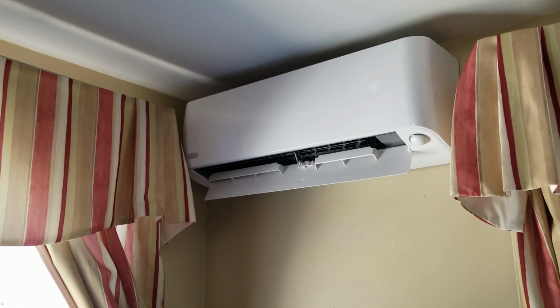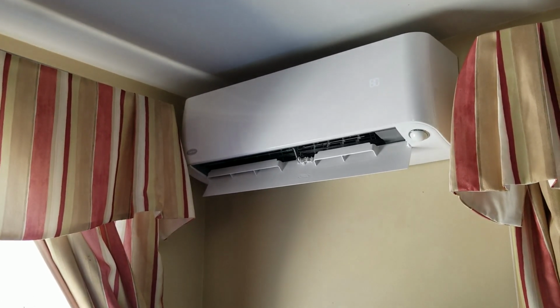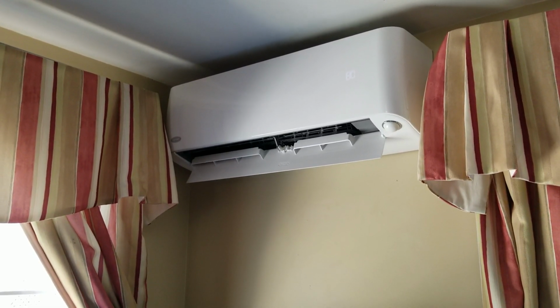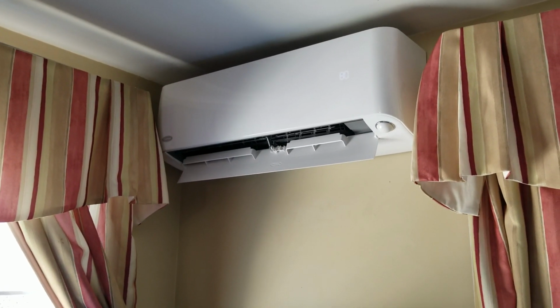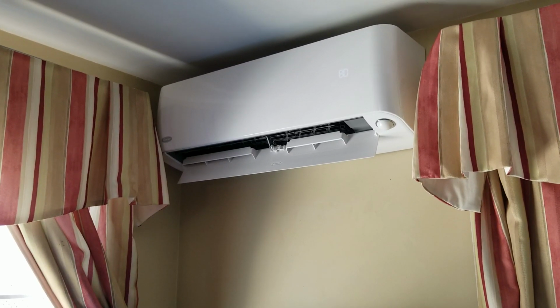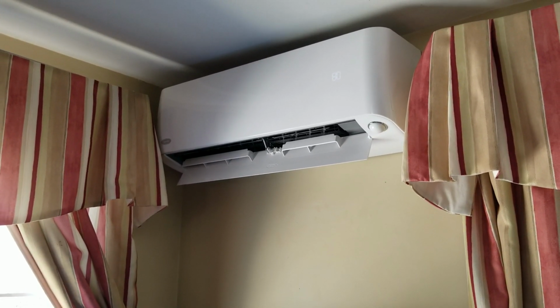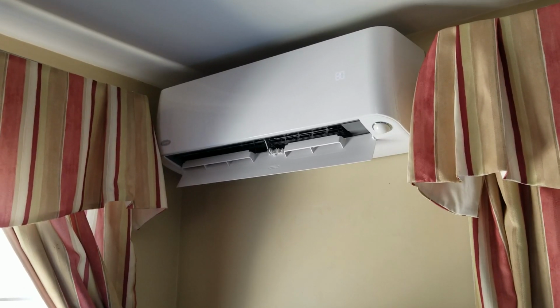So since December now, it's been an ongoing issue with Carrier to explain to me why other people seem to be having success with these heat pumps and I'm not. I have hired 2 different companies to assess these heat pumps, because Carrier tells me they're working well, but I'm not getting any heat. So I had an LG installer come and look at them, and he says they should be working a lot better than they are. I've also brought in a Fujitsu company to look at them, and he says they're oversized. I got too much, and if he put in a system, he'd put in a smaller system and would create more heat than this.